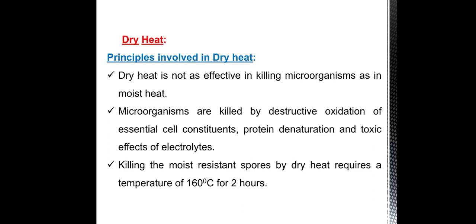Dry heat is not as effective in killing microorganisms as moist heat. Microorganisms are killed by destructive oxidation of essential cell constituents, protein denaturation, and toxic effect of electrolytes. Killing the most resistant spores by dry heat requires a temperature of 160 degree Celsius for 2 hours.